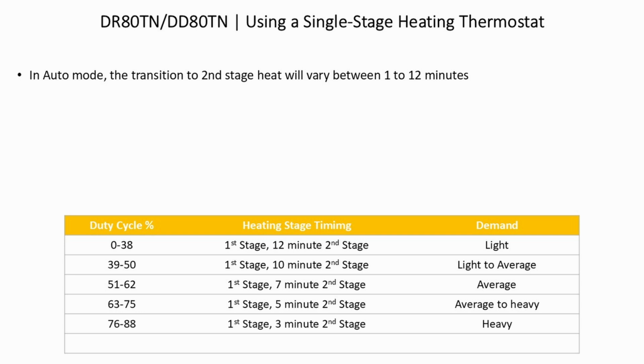From 76 to 88%, first stage heat for 3 minutes, then transition to second stage. That would be a heavy demand. For 89 to 100% duty cycle, first stage heat would come on for 1 minute, then transition to second stage, also for heavy demand.